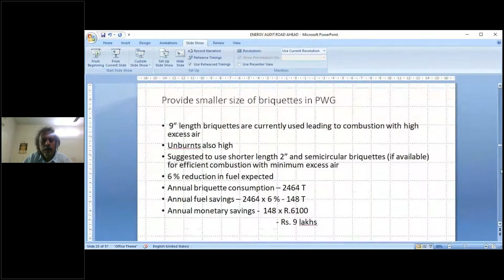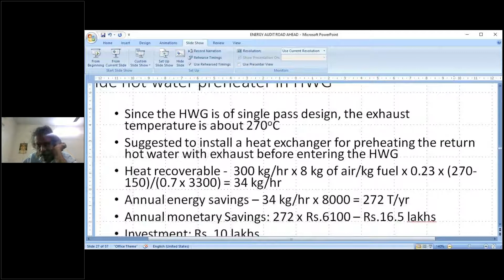And there is another case where, earlier they were using a briquette fired boiler, just sawdust briquettes. Sawdust briquettes are used as fuels. If you use a bigger size briquette, unburns were found to be more. So what we did was slice these briquettes. During the purchase itself, we asked the supplier to slice this into a maximum 2 inch width. Instead of having a 6-inch or 8-inch, we asked them to make it 2-inch. As a result, the combustion improved and the unburned losses reduced. So this is a typical example of how the size is important when it comes to complete combustion. The lower the particle size, the better the combustion.